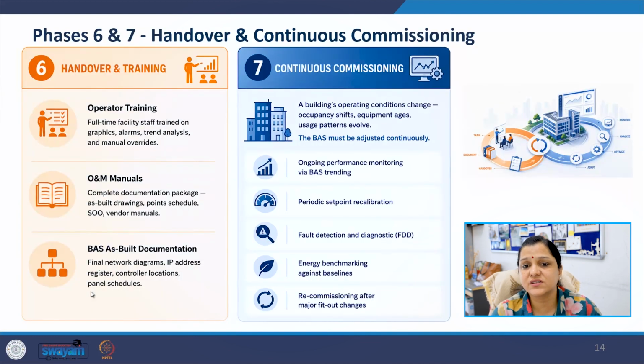Handover and continuous commissioning. After commissioning comes handover. At this stage, facility operators must be trained properly. They should understand graphics, alarms, trend analysis, and manual override procedures. Complete documentation must be delivered. This includes as-built drawings, network diagrams, point schedules, and vendor manuals.